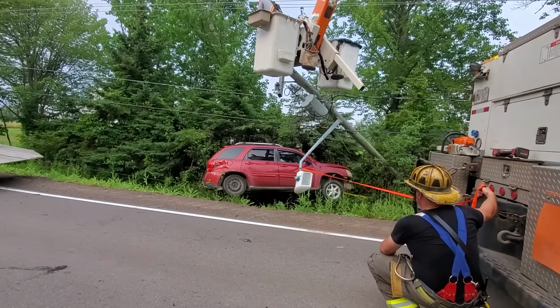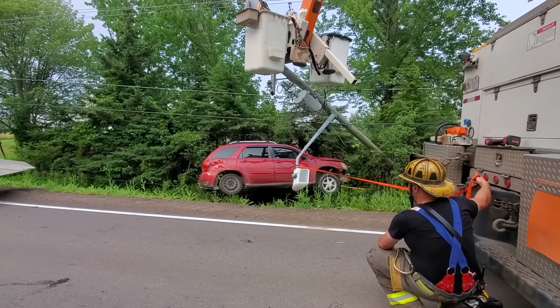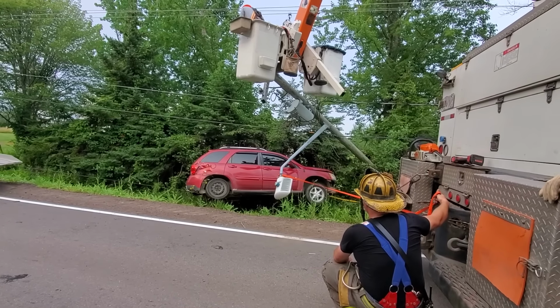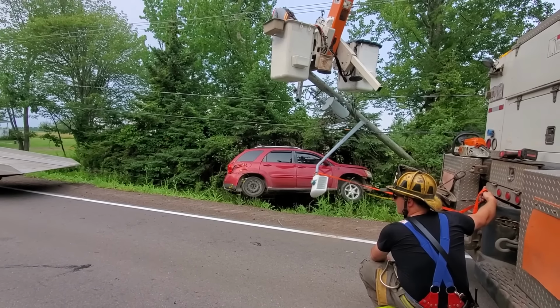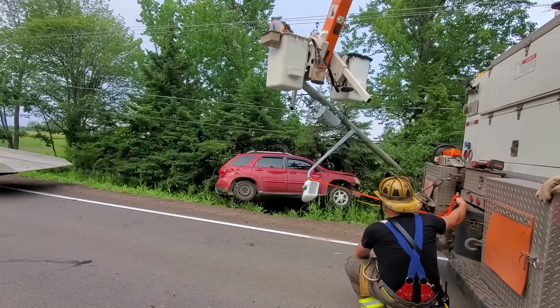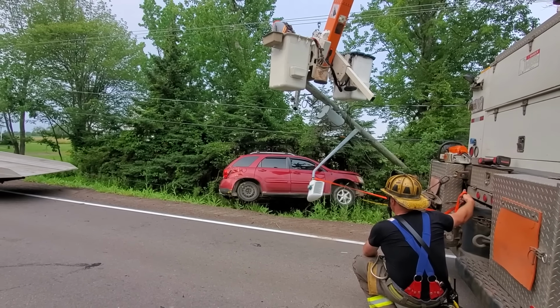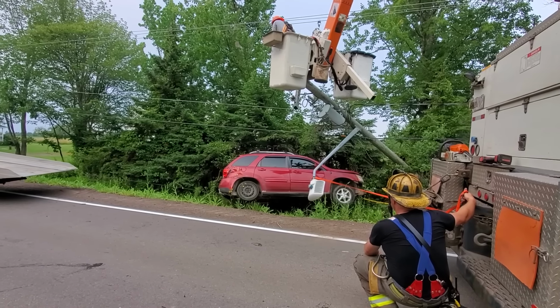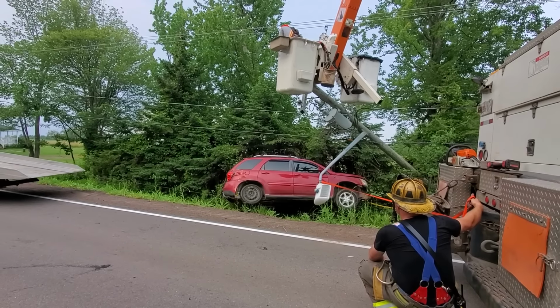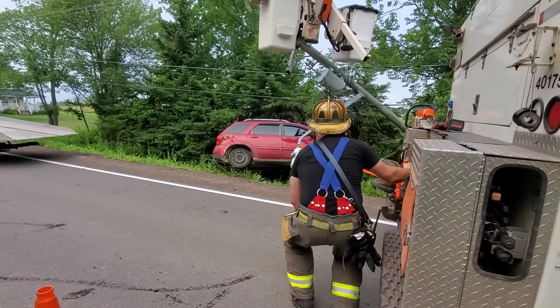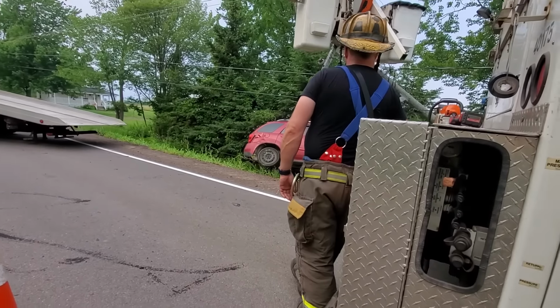One of the firefighters on scene mentioned that the cutout was open to the transformer. I showed him that even though the cutout was open, that simply disconnected power to the transformer, but the lead was still alive. That presented a very dangerous situation to anyone involved. Luckily, we were close by on that one.